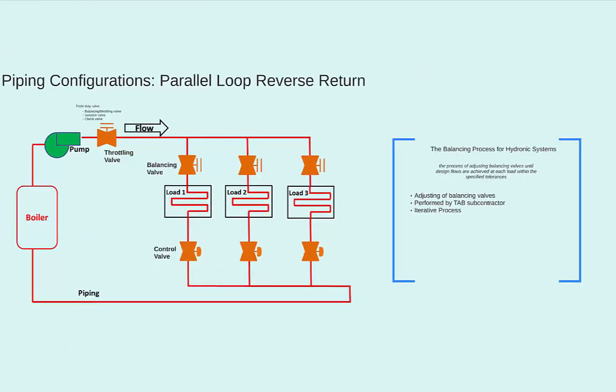So the balancing process is an iterative process of adjusting the balancing valves at the coil as well as the throttling valve on the discharge of the pump. Once the TAB subcontractor completes this process, all such valves are not adjusted anymore, unless there is some renovation to part of the system that would warrant a rebalancing effort.